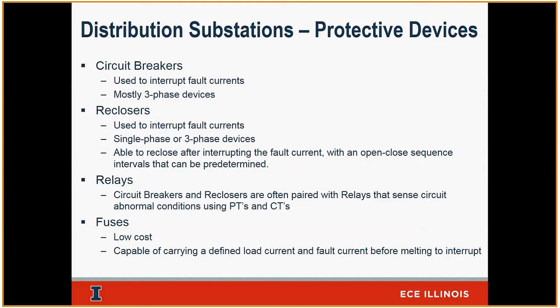So circuit breakers are protective devices. They're sitting there looking at the current. At any time the current crosses a threshold that you as engineers decide is dangerous or limiting, the circuit breaker will open. It will interrupt that current. So right away it will open. These will open in oil or in vacuum. The newer designs of a lot of our circuit breakers and reclosers will open in vacuum, so that we don't see that discharge happen in that arc. It will open and de-energize that line automatically. That's mainly what a circuit breaker is for.